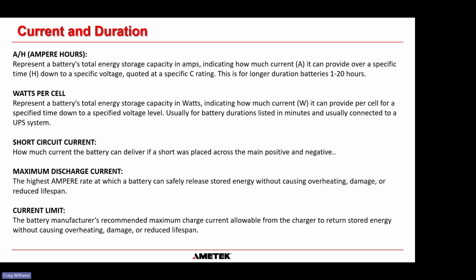Maximum discharge current is the highest ampere rate at which a battery can safely release its stored energy without causing overheating, damage, or reduced lifespan. Current limit is the battery manufacturer's recommended maximum charge current allowable from the charger to return stored energy into the battery without causing overheating, damage, or reduced lifespan.